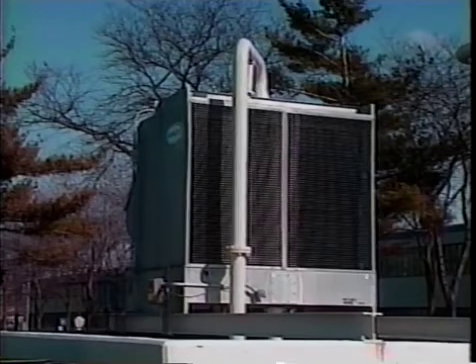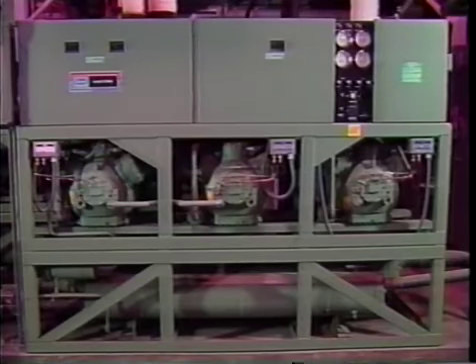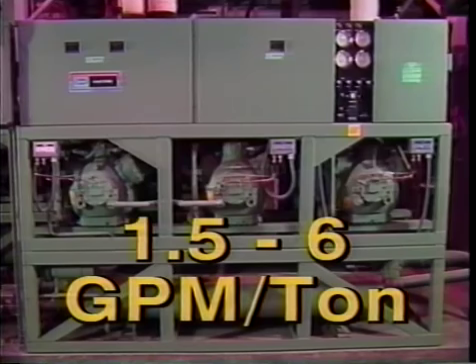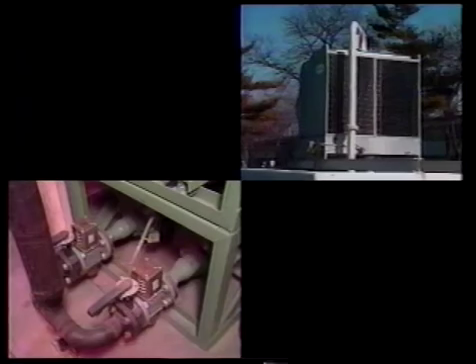Here, the temperature of the water is controlled by cycling the tower fans, and the total flow at the condensers is set at a constant flow rate, typically anywhere from 1.5 to 6 gallons per minute per ton. Regardless of which system is used, water flow rates will have been established when the equipment was selected.